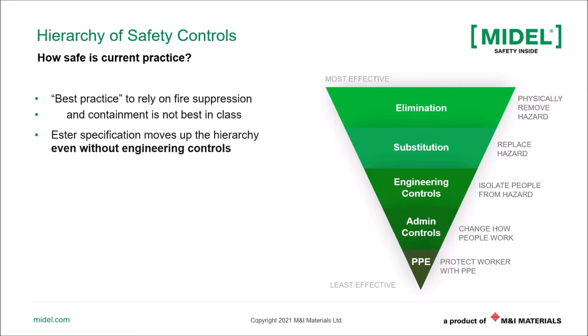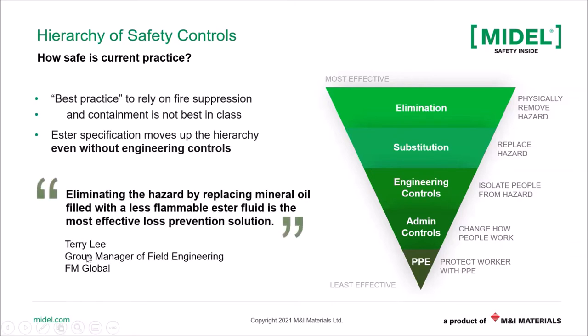So then the question is always, how safe are the current practices? The best practice to rely on fire suppression and containment is not the best in class anymore. Esters move up the hierarchy even without the engineering controls. So I want to show you a quote from Terry Lee, who's the group manager of field engineers at FM Global. He said that eliminating the hazard by replacing mineral oil with less flammable ester fluid is the most effective loss prevention solution.